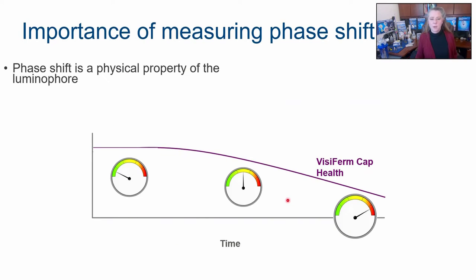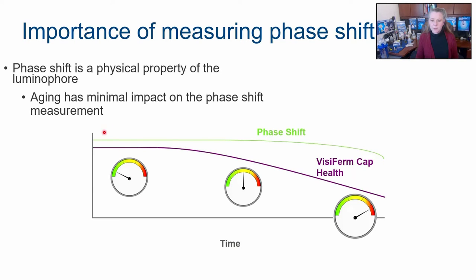Phase shift is a physical property of the luminophore. The luminophore is a consumable. It will get used up over time. You add light, the luminophore gets used up. Those caps have a lifetime. But what's really cool is that the phase shift is actually highly measurable way, way beyond the death of your cap. So your cap might actually be down to 50% health and you're still getting a very strong phase shift. That means that these probes can measure on a single cap for a fairly long time. And that means they're robust.